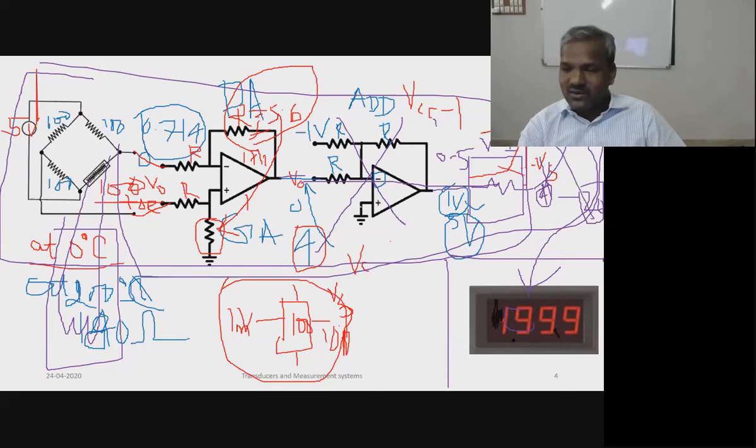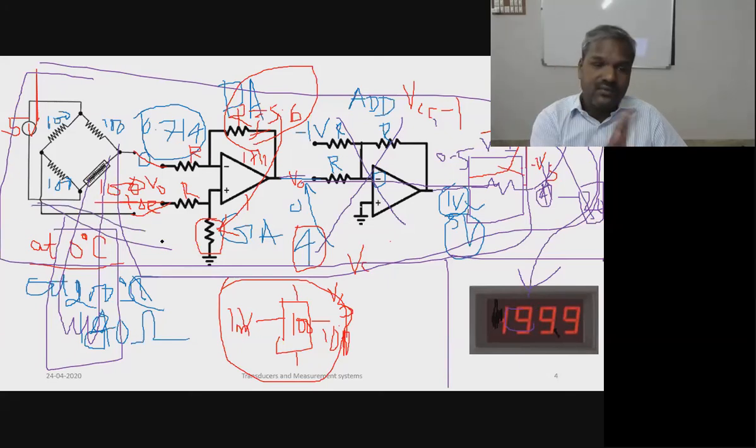What will it show? With the cut itself, it will show 0. Suppose the RTD fails. This is a real dead zero. When the RTD itself fails, what is the output available at the control room? Then also we are getting 0 only. So if the sensor fails, we are getting 0, right? To avoid such error, we have the range of 1 to 5 volt.